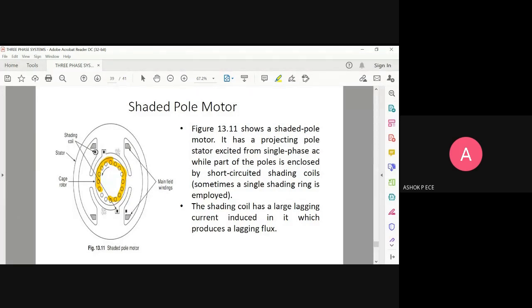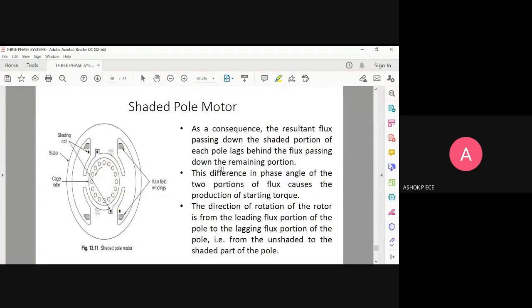One shading coil will be present inside the pole and one will be present adjacent to the rotor. Same way on the other side — one is present adjacent to the rotor and one is present inside the pole. What happens because of the shading coil is that the resultant flux passing on the shaded portion of each pole lags behind the flux passing on the remaining portion.